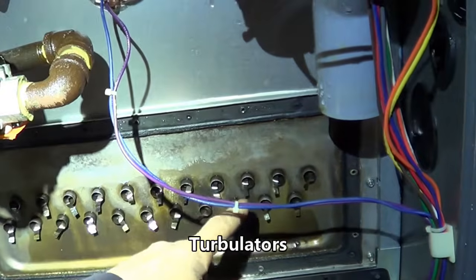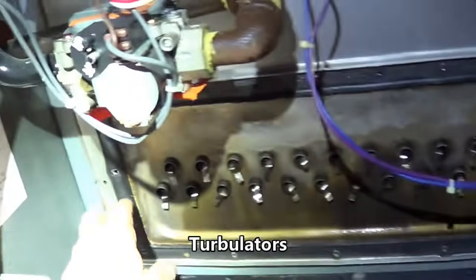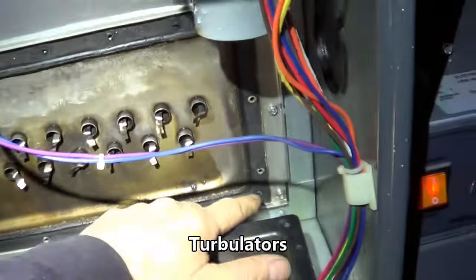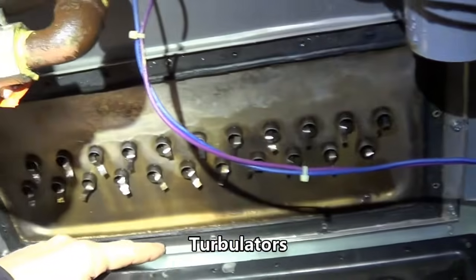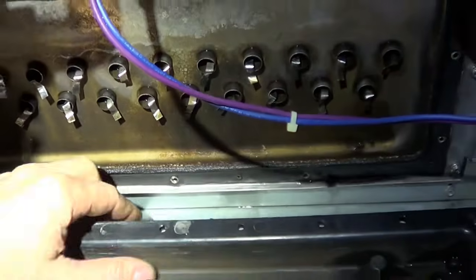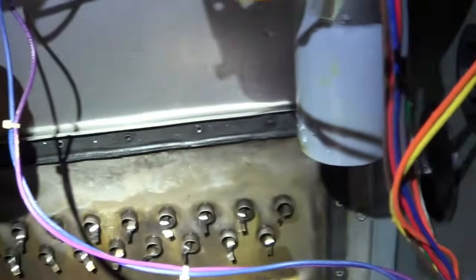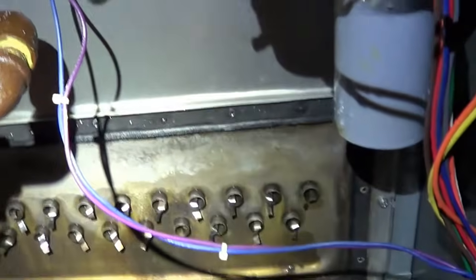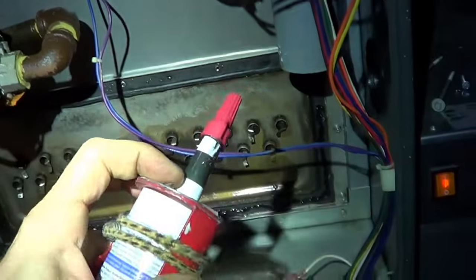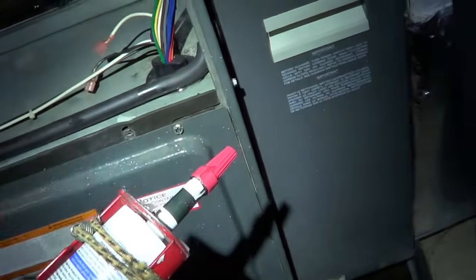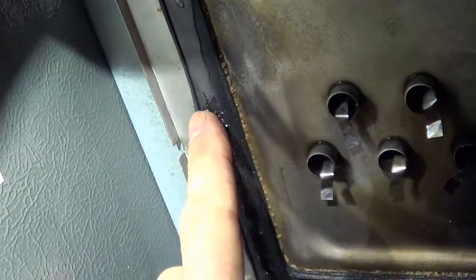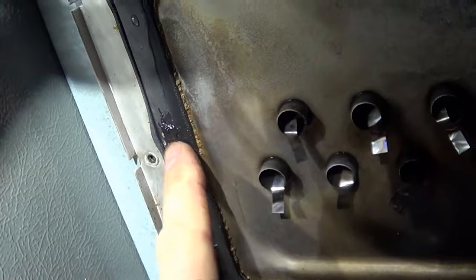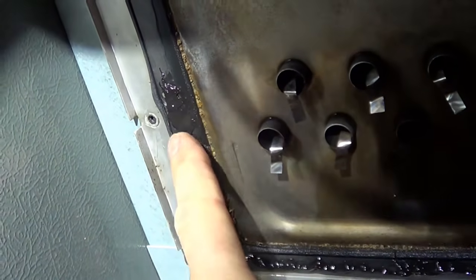All the swirlers are put in, heat exchangers cleaned. This one has a rubber gasket, and it's important that it doesn't leak, especially on the bottom. Otherwise it's just going to drip condensate, start rusting out the furnace. So I'm going to add some silicone just to the bottom. The top's going to be fine because it's not going to leak water on the top. Little tip, if you want your silicone to last, put a wire nut on it as the seal. It can last for months like that. So, and then I'm just going to spread it out thin. A little bit of a seal.